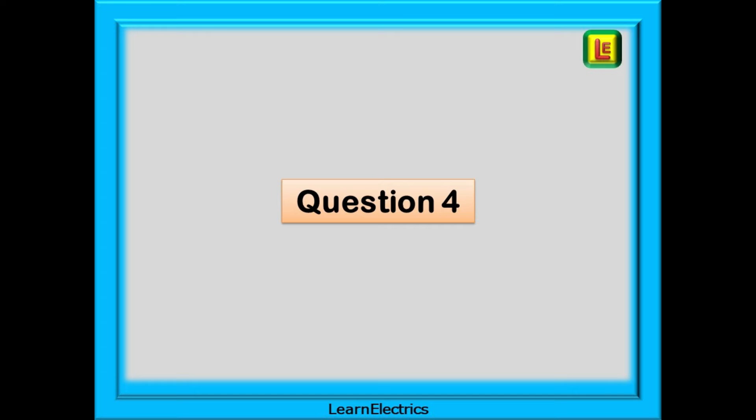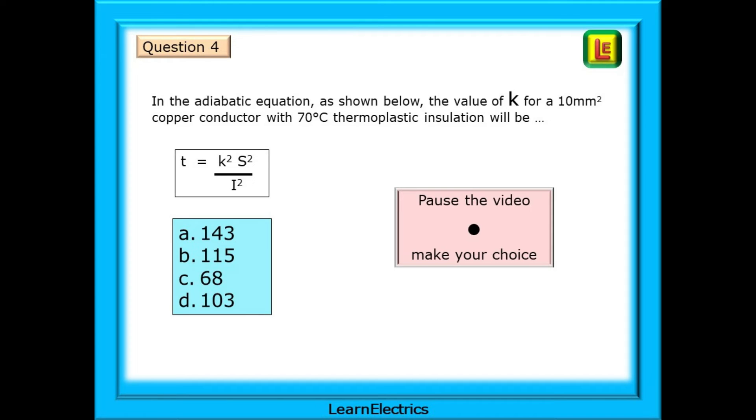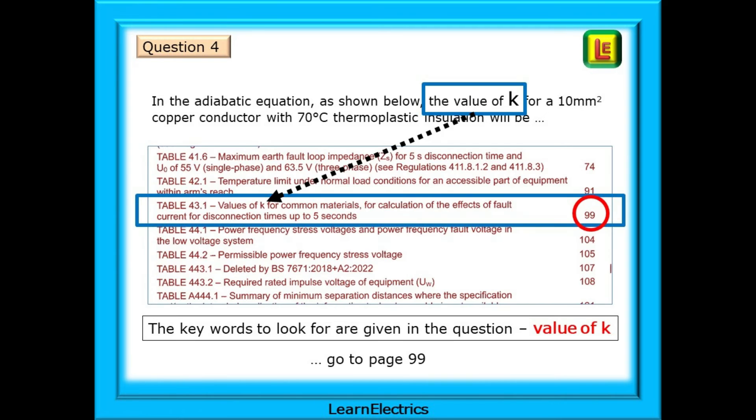Question four shows a calculation, but the question is not a calculation. Always read the question carefully. In the adiabatic equation, as shown below, the value of K for a 10 square millimetre copper conductor with 70 degree thermoplastic insulation will be what? The equation is shown only so that you know which K they are making reference to. You will need a table of K values to find the answer. Pause the video. Find the table.